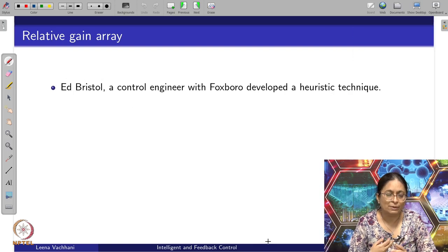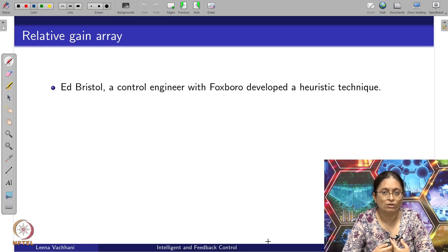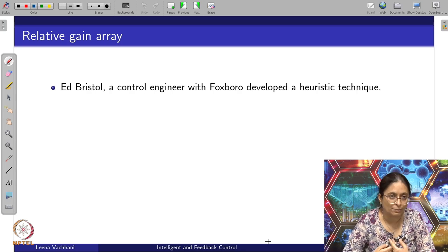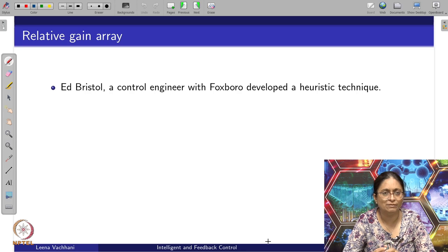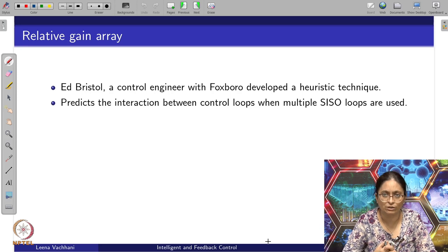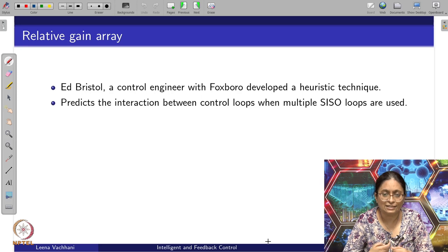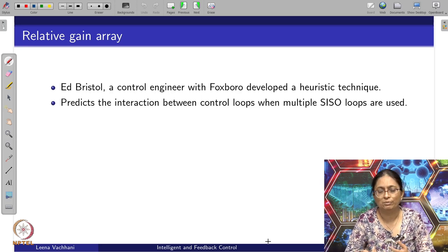So let us come up with a particular method called Relative Gain Array, which uses these effective gains in order to solve the variable pairing problem. This was developed by Ed Bristol, a control engineer from Foxboro, as a heuristic technique. It predicts the interaction between control loops when multiple SISO loops are used — because if these interactions are minimal, I will be able to use the multiple SISO method.